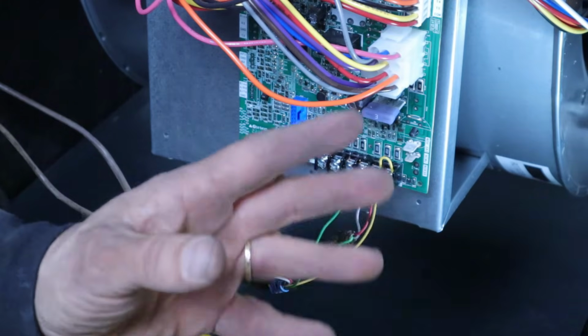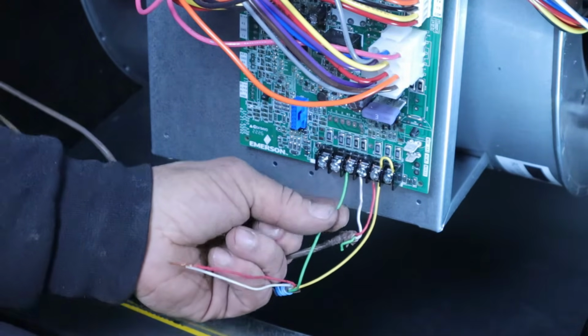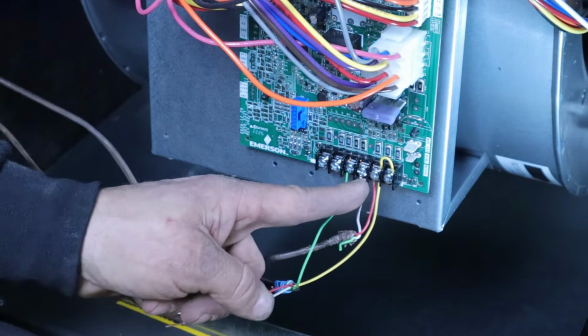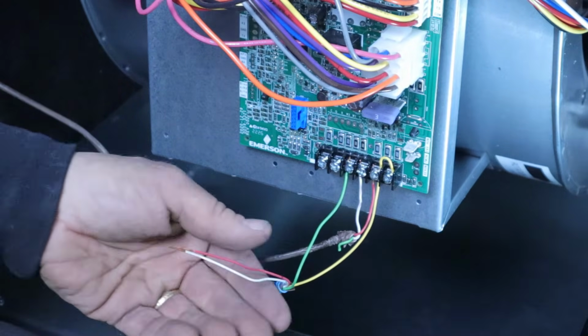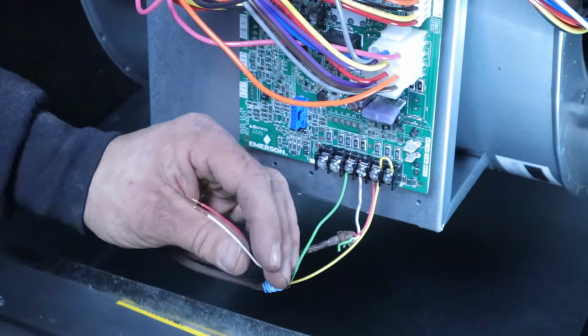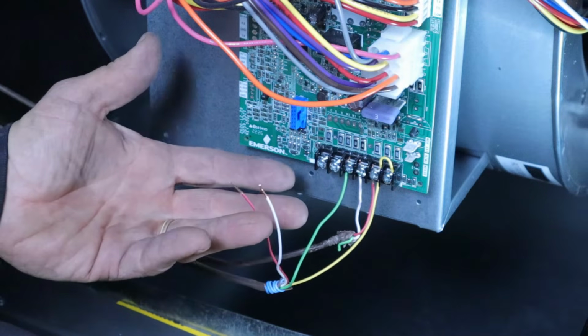So if you ever install a Nest thermostat and you don't have enough wires, you can actually use that green wire as a common. You just disconnect it, put it on your common, and then hook common up to your thermostat with the green wire, and your heating and cooling system will still work.